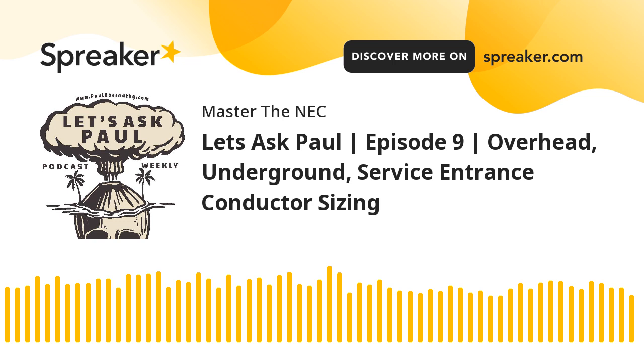Now, first, 230.90 says where required. It says each ungrounded service conductor shall have overload protection. Okay. Now, 230.90(A) says ungrounded conductors. It says such protection shall be provided by an overcurrent device in series with each ungrounded conductor and has a rating or setting not higher than the ampacity of the conductor. Okay. So you've sized your conductor. You're sizing everything based on your loads, your calculated loads, and your overcurrent protection rating is not higher than the ampacity of your conductor.